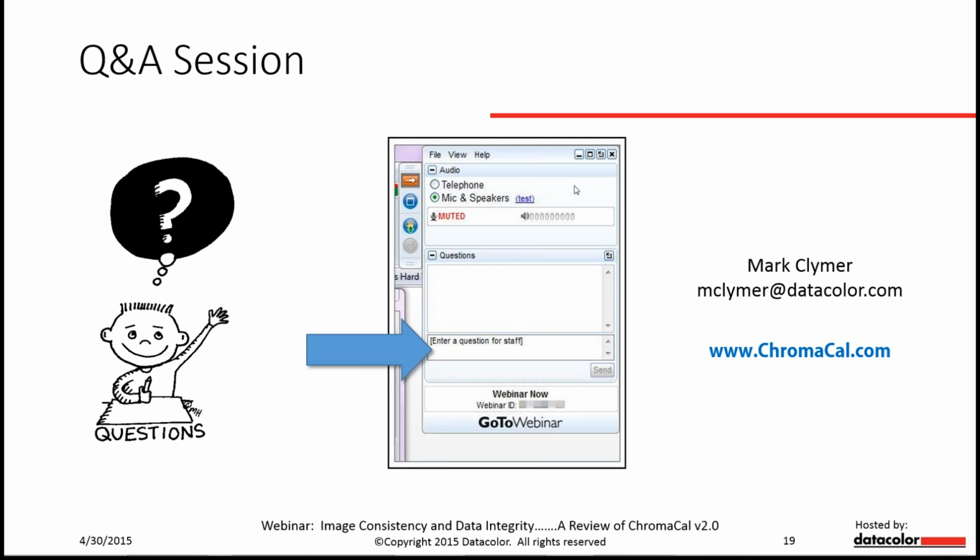Let's see, any other questions? Here's one. Recent FDA draft guidance for whole slide imaging systems mentions color sampling sizes greater than 100 pixels. What is your sampling size? I'll address that as well. I think this refers to those little boxes in the matrix image, and the exact number of pixels really depends on the pixel density of your image, but generally we're sampling over 700 pixels for each color circle that's in that matrix. So that's well in excess of the recommended lower limit for the FDA.